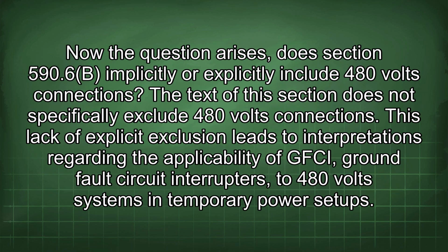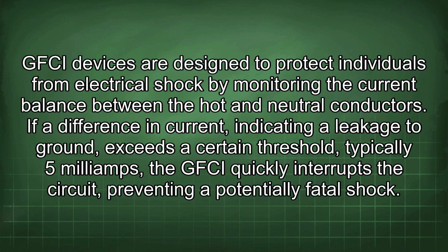Now the question arises: does Section 590.6b implicitly or explicitly include 480 volt connections? The text of this section does not specifically exclude 480 volt connections. This lack of explicit exclusion leads to interpretations regarding the applicability of GFCI, ground fault circuit interrupters, to 480 volt systems in temporary power setups. GFCI devices are designed to protect individuals from electrical shock by monitoring the current balance between the hot and neutral conductors. If a difference in current, indicating a leakage to ground, exceeds a certain threshold, typically 5 milliamps, the GFCI quickly interrupts the circuit, preventing a potentially fatal shock.